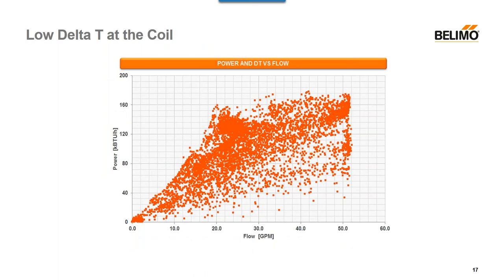Looking at actual field data from an installed valve — all the orange squares are data points. At around 20 GPM we see about 130 kiloBTUs, and at 50 GPM we also see about 130 kiloBTUs. The difference between 20 GPM and 50 GPM is a marginal ~10% increase in output. We realized that we could operate somewhere in between, leveraging that wide coil power band. That's one of the benefits of what the energy valve does — it recognizes and really optimizes the sweet spot of that coil.